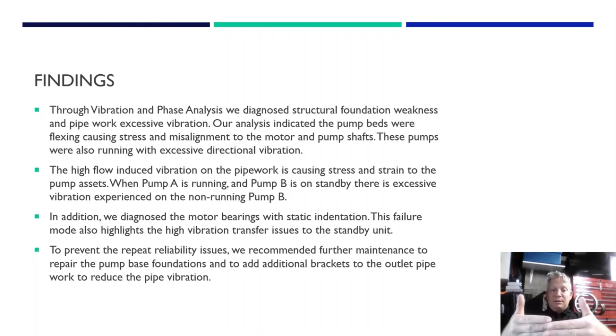So our recommendations to resolve that was to concrete in the frames, add stiffeners up to the pipework, and if they can, put in some sort of bellows, gusset, basically, just to absorb some of the motion, so when the pipe is moving, it's not going to transfer to the other pump.